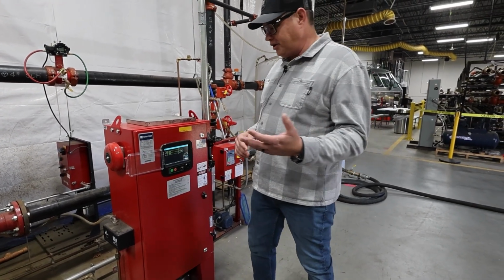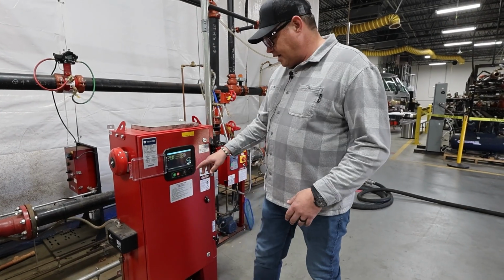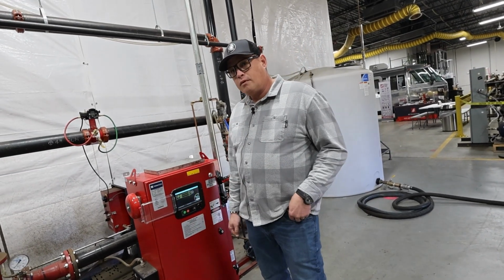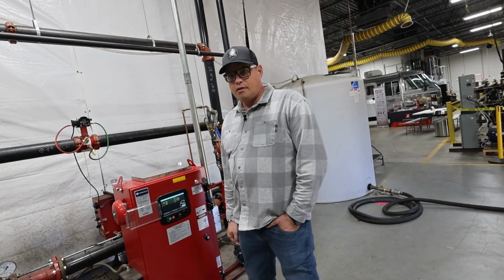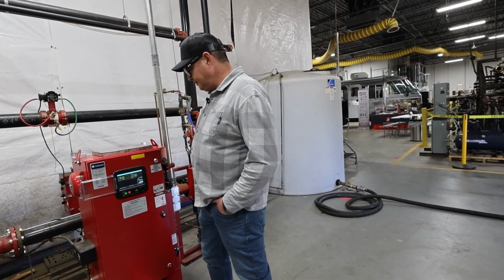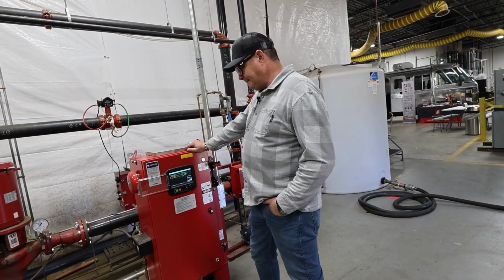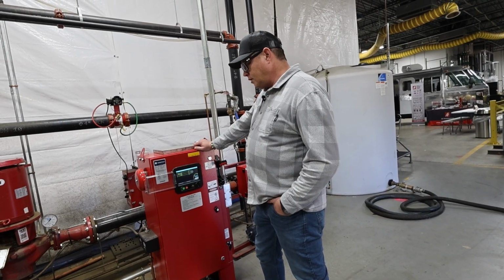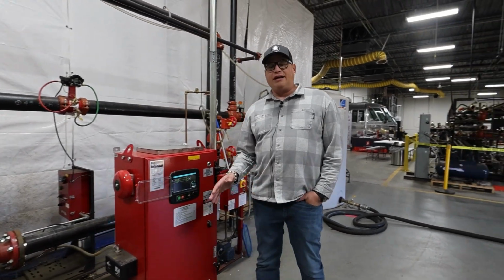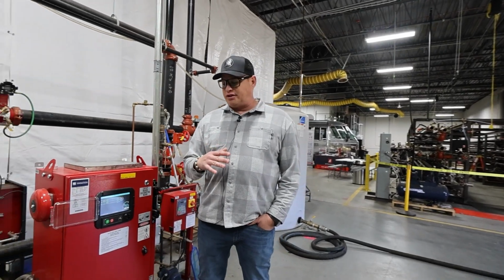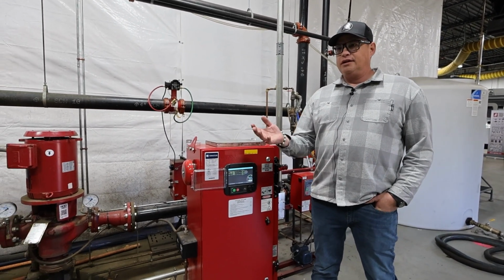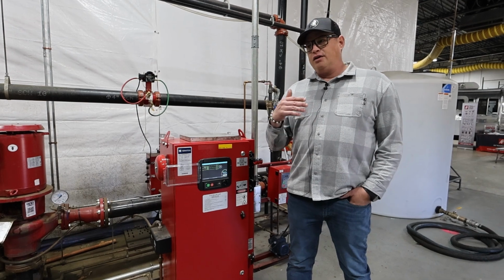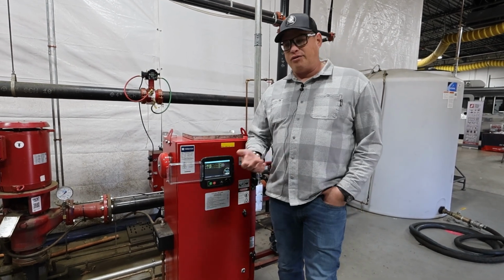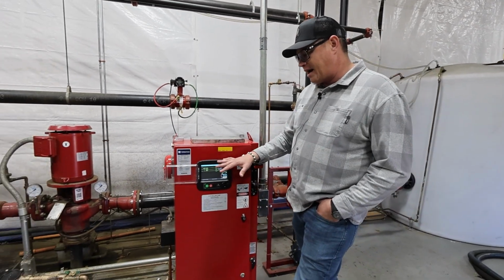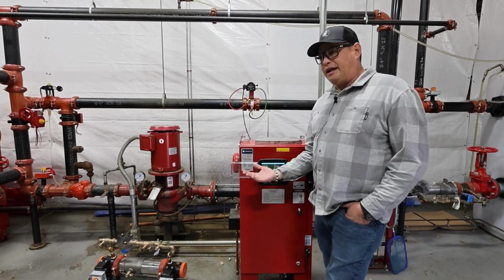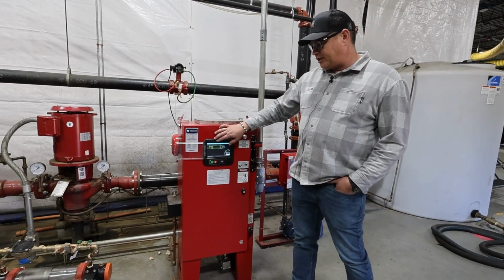It just depends on your municipality whether or not that's allowed. Now the automatic shutdown can be set up on a timer as well, right? Yes. So minimum run time, 10 minutes, 5 minutes, etc. Yes. I know it's not allowed by NFPA. Was it a one-time allowed by NFPA, or is it not anymore? Well, no, automatic shutdown is allowed. It's just depending on your jurisdiction. There's certain jurisdictions that don't want it because there's some conflicting information in NFPA. One part of it says you have to have a competent person in the room at all times during any and all fire pump operations. Yep. But depending on where you are, they will allow for the automatic shutdown.